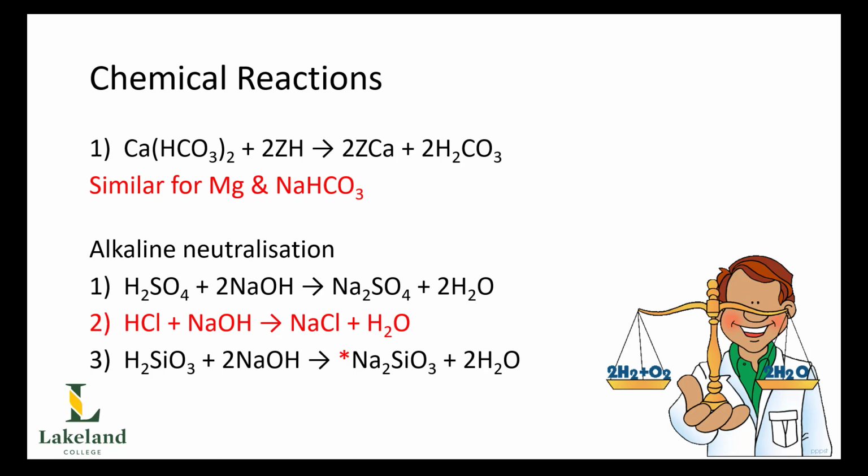That's all the same. Now I've just selected one of those equations here to display, and that's the one for calcium bicarbonate, but it would also be the same for magnesium bicarbonate as well as sodium bicarbonate. And this is going to form zeolite calcium, and also our carbonic acid, H2CO3. And that's what's going to be stripped off in our degasification tower by the process of aeration.